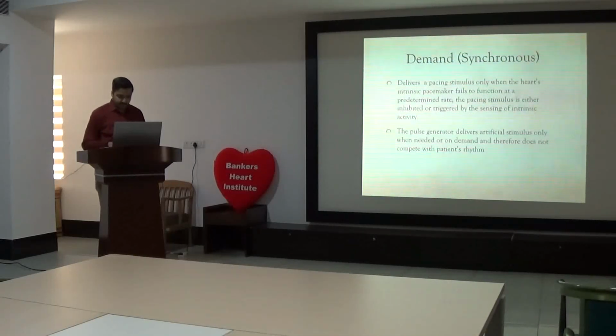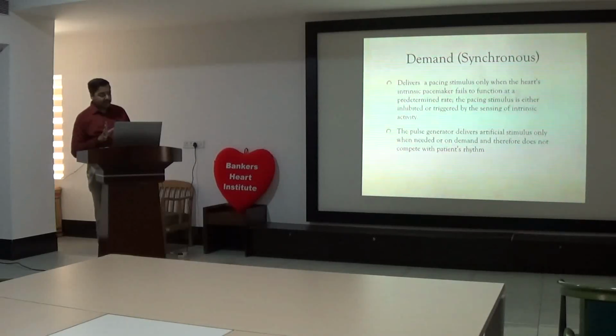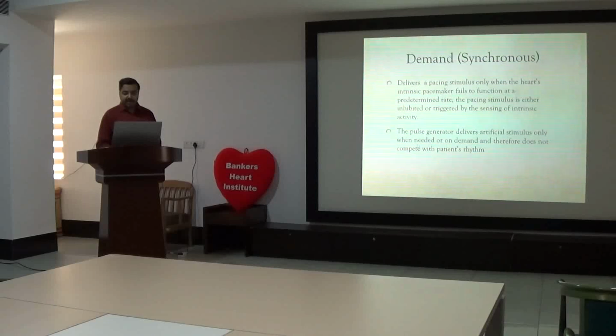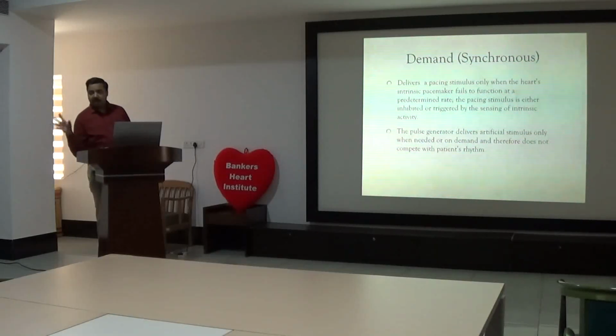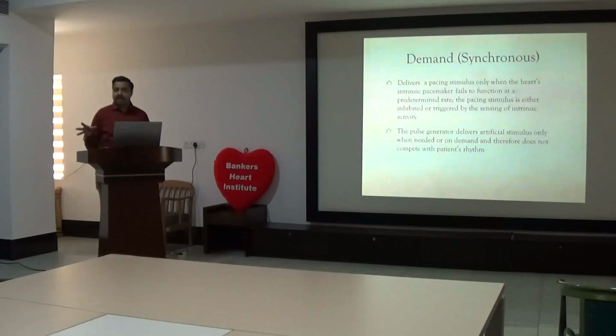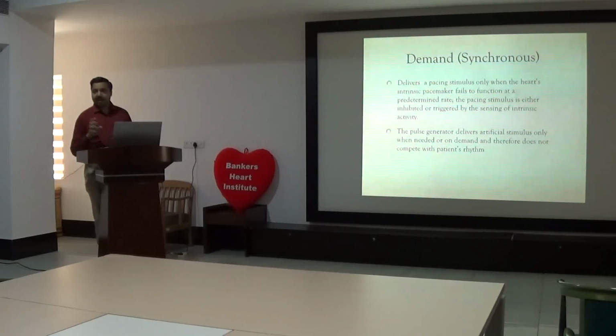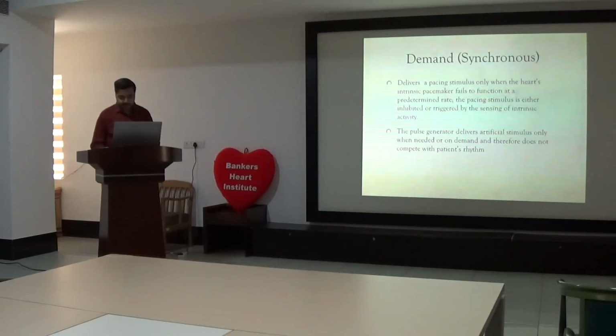Demand pacing. Here comes the role of sensitivity. The pulse generator delivers an artificial stimulus only when needed, or on demand, and it does not compete with the patient's rhythm. Say the patient is in temporary heart failure because of some hyperkalemia, and you implanted a pacemaker. Once the hyperkalemia corrects, the patient's intrinsic depolarization will start. At that time, if you set a sensitivity of 0.25 or 0.5, and once the patient's electrical activity goes beyond that particular millivolt level, then the pacemaker will go into only sensing mode, and it will allow the patient's intrinsic heartbeat to occur. This is a good function actually. This is required, and most of the time we set the pacemaker on this function.